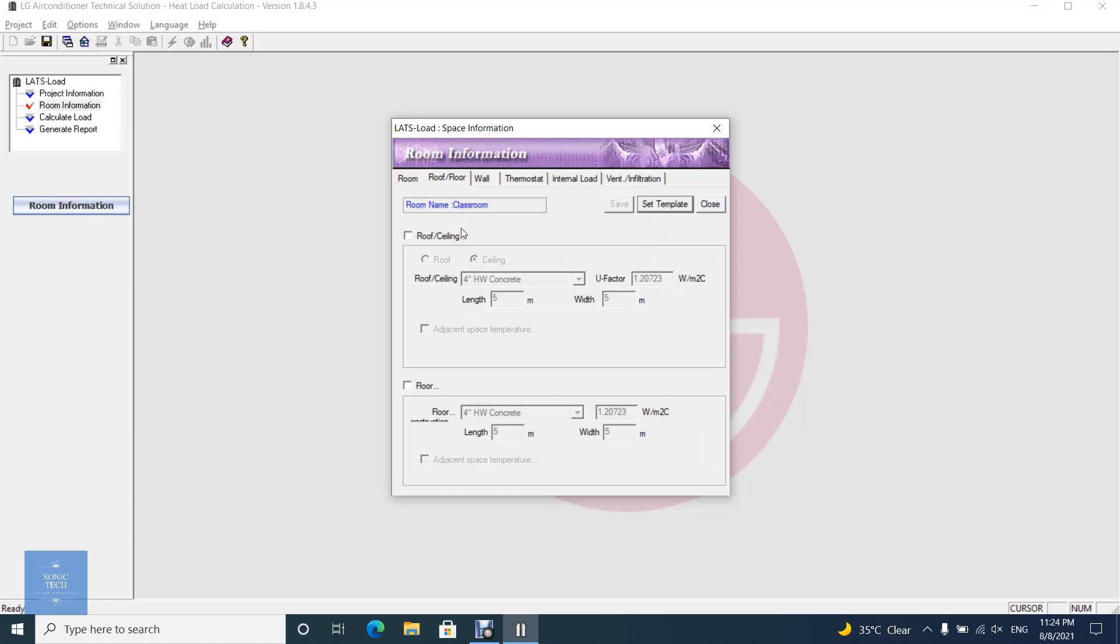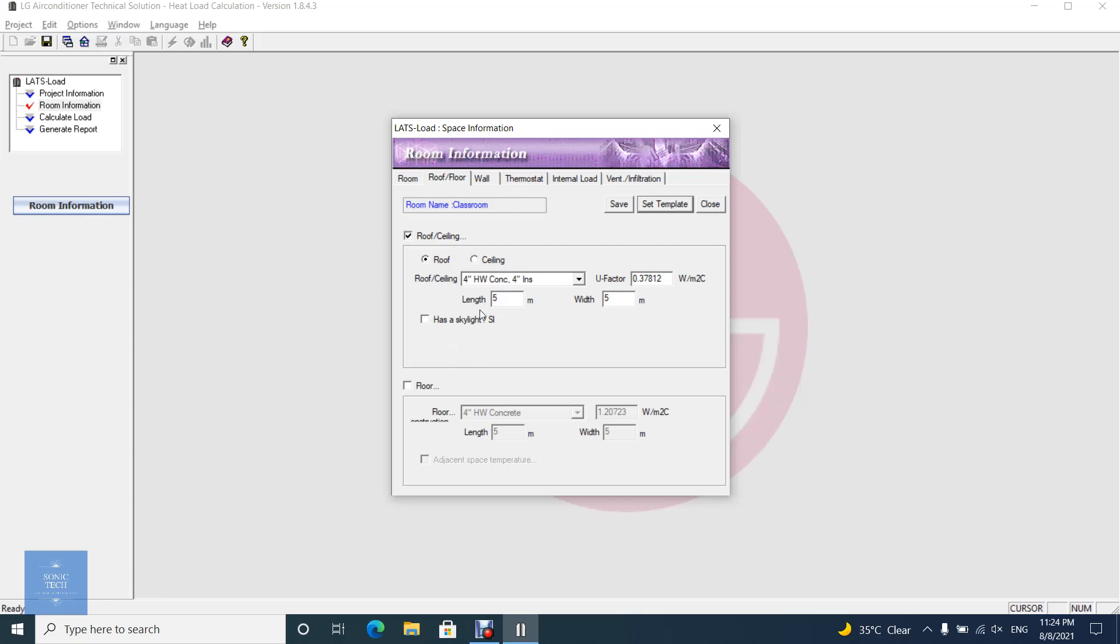In the roof and floor tab, you could set roof, ceiling and floor attributes. By default, the room template information you specified is displayed in the dialogue. If you want to change construction attributes at one time, use Set Template button. Roof corresponds to external load, ceiling and floor corresponds to partition load.